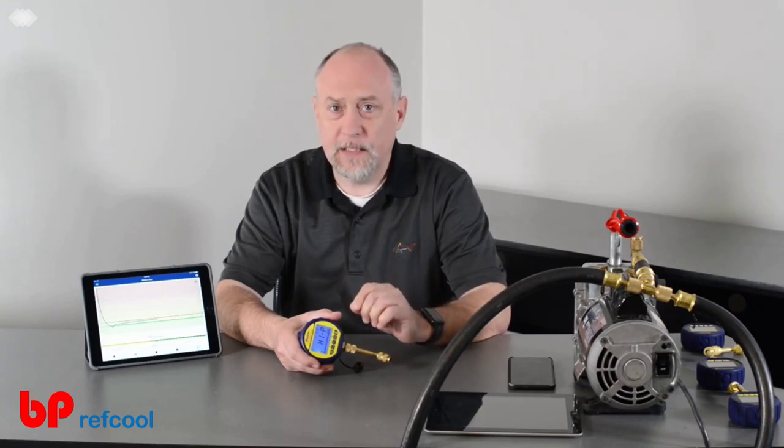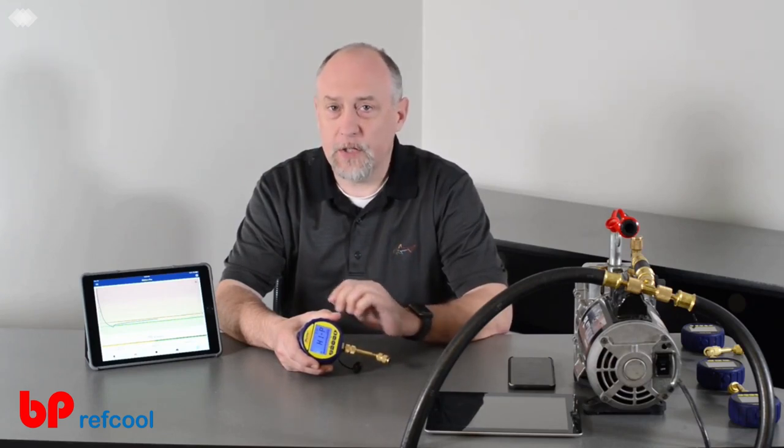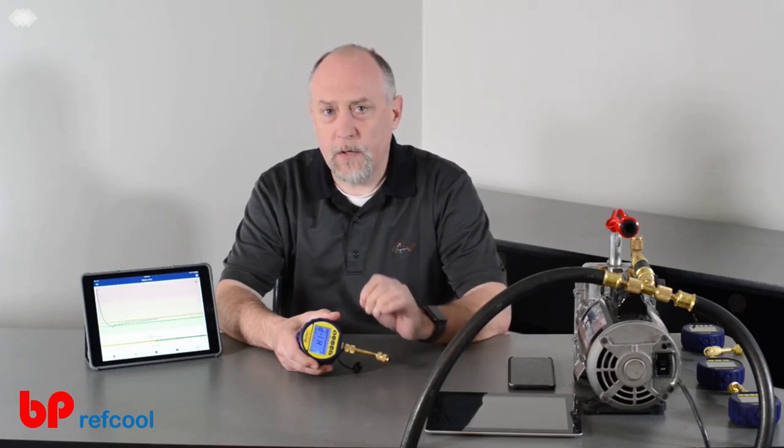The Bluvac Plus Professional provides us with a ton of information when paired with the application. It really documents a process that deserves documentation. There's nothing more important than a proper evacuation. When you start that air conditioning system up, the only thing you want to have in there is refrigerant and oil.